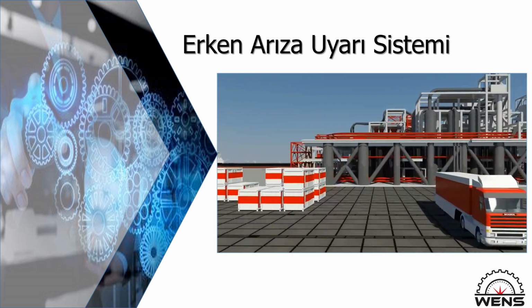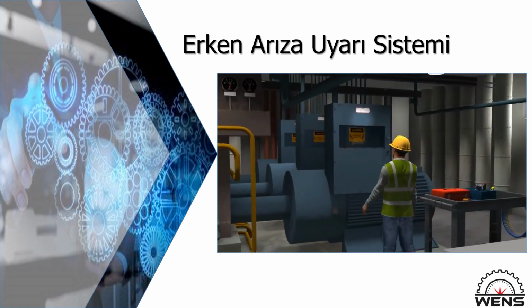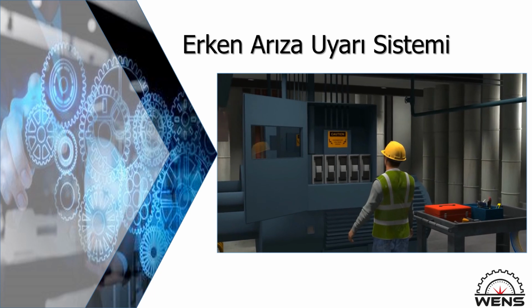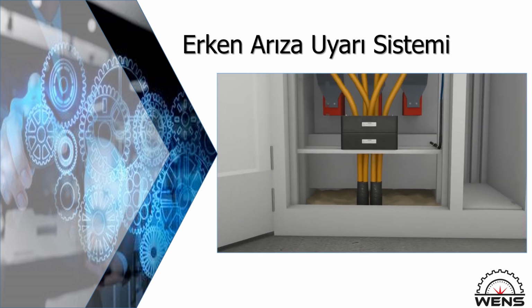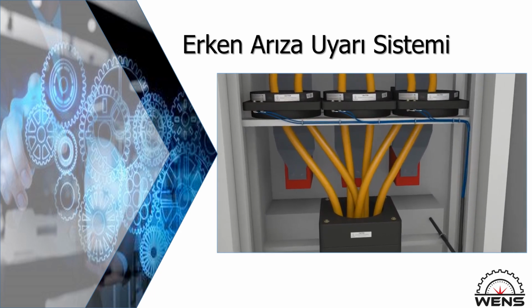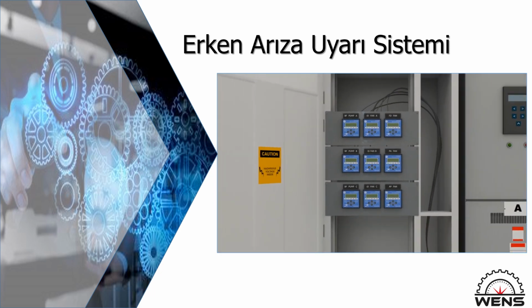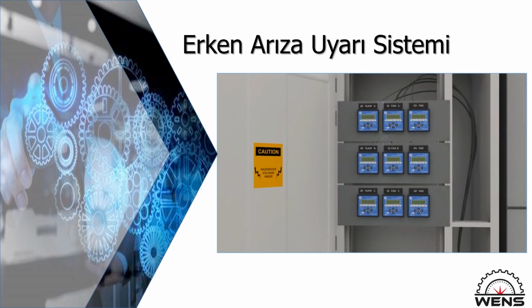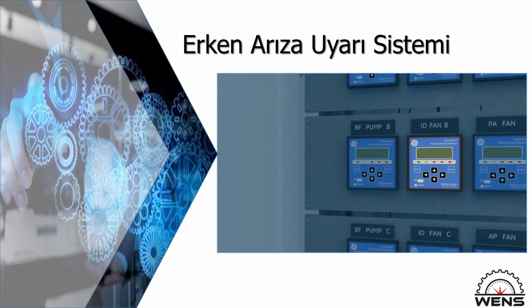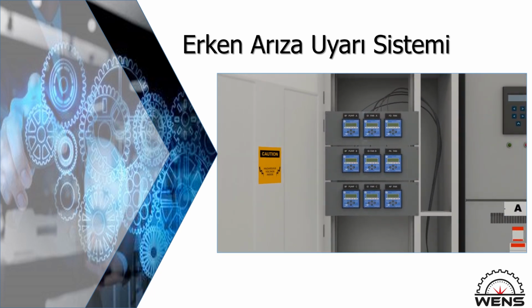Let's take a closer look at a refinery. Stacked with motors, pumps and filters, it's not always directly accessible for checks and maintenance. Anom Alert detects anomalies by measuring the current and voltage signals from the electrical supply to the motor. As a result, it detects both mechanical and electrical anomalies. It also monitors electrical parameters, such as voltage and current imbalances and power factor. What's more, it can detect changes in the motor load due to anomalies in the equipment being driven, or issues like cavitations or plugged filters and screens.